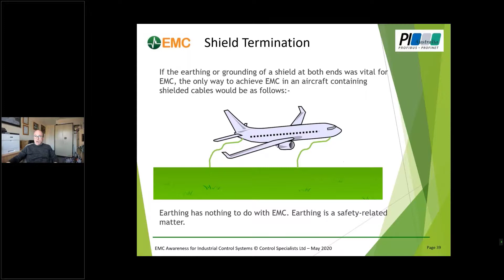If we've got a loop that comprises the shield and its connection at both ends to some kind of bonding infrastructure, then there will be current flowing in, and that current will generate a magnetic field 180 degrees out of phase with the magnetic field that's causing the problem. That's one of the mechanisms by which the shield works.